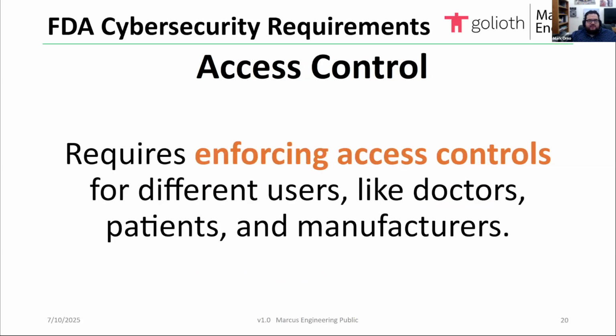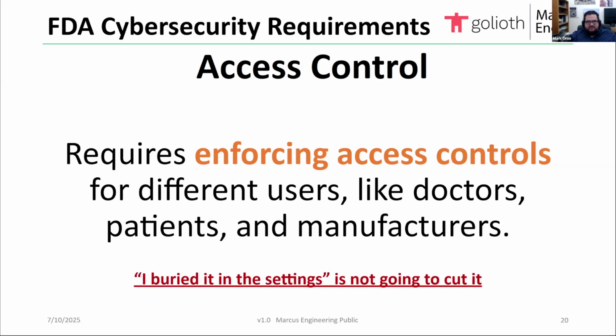And the next one, access control. They require you to enforce access controls for different users, like doctors, patients, and manufacturers. So your manufacturer settings, things that should never be changed except by the OEM, cannot be accessible to your doctors. And things like patient settings can't change stuff that a doctor should only be able to change. And one thing I see is "I buried it in the settings." I buried it in the settings is not going to cut it. That does not meet the FDA's requirements for enforcing the right access control, enforcing the right separation of responsibilities.